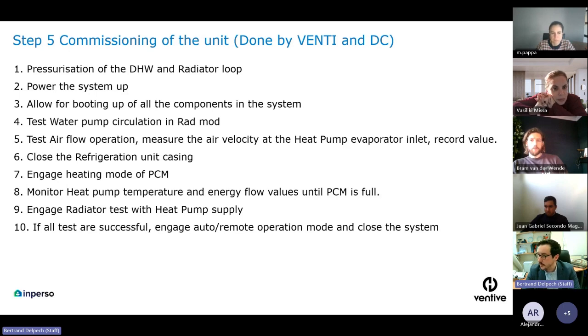And again, similar with the booting of all the components, we're going to go through a water circulation test where we can also remove all of the air inside the radiator. We're going to test the airflow operation and check how much pressure drop we have in the system, so we can set up the velocity of our fan to the proper value.